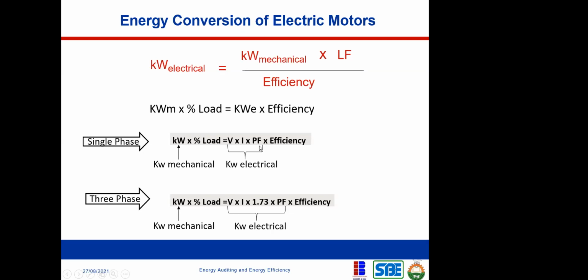Then you have your kilowatt electrical. When you open it up, your kilowatt electrical is voltage times current times power factor, and then of course times your efficiency. For three-phase, it's the same thing, only that you introduce the square root of 3, which is 1.73. If you punch the square root on your calculator, you get 1.73. So let us take note of these formulas, please.